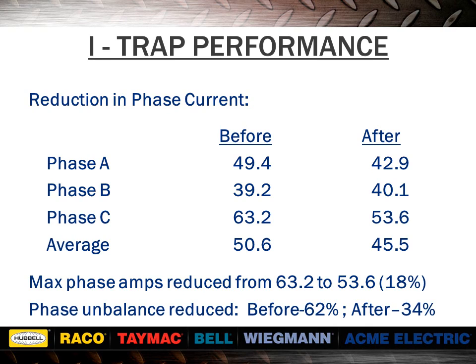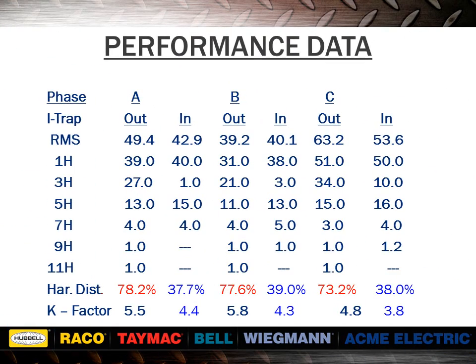The I-TRAP helps reduce unbalance in the phases, which helps reduce neutral current. The I-TRAP is not a harmonic filter, but it does tend to reduce total harmonic distortion in the phases. It also slightly reduces the k-factor of the system, which allows the supply transformer to operate a little cooler, resulting in longer life. If this transformer is ever replaced, it is recommended that it be replaced with a k-factor unit.